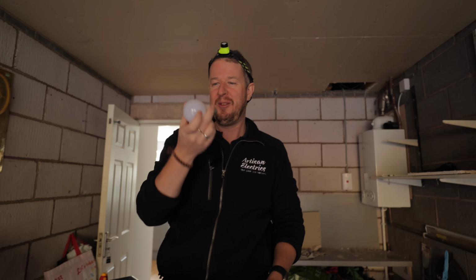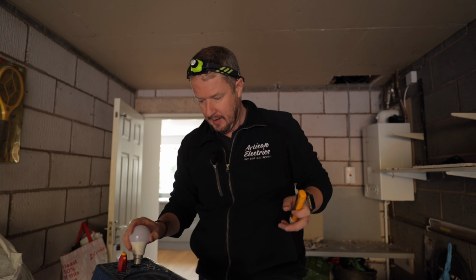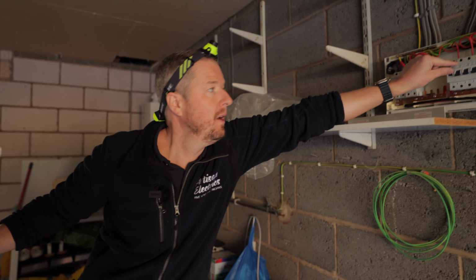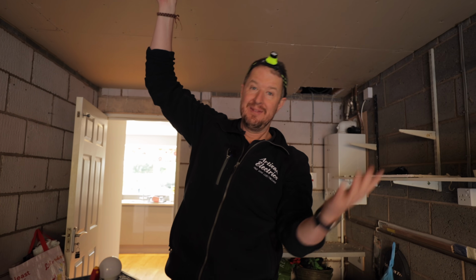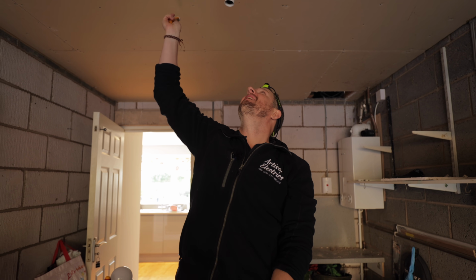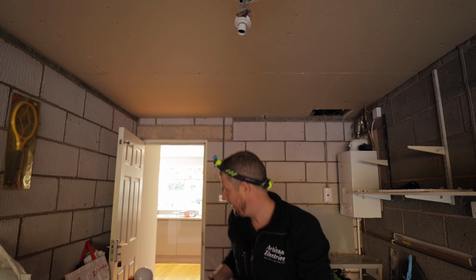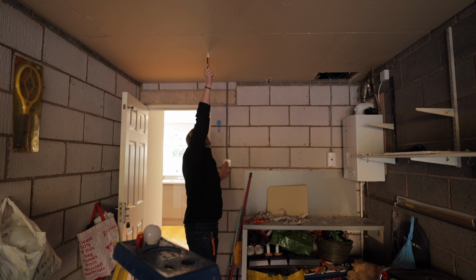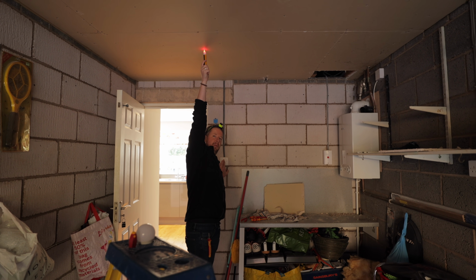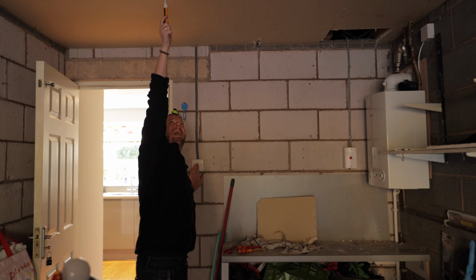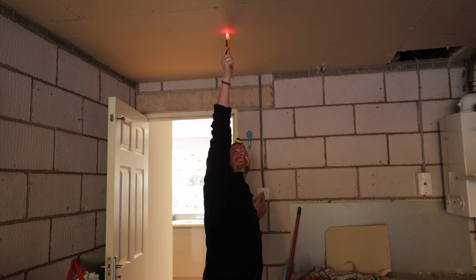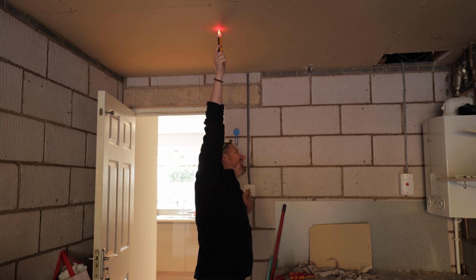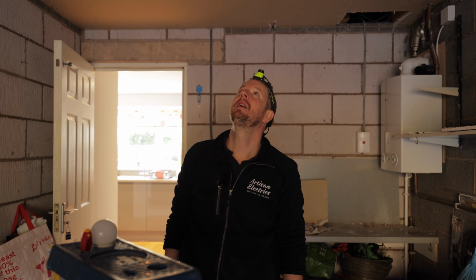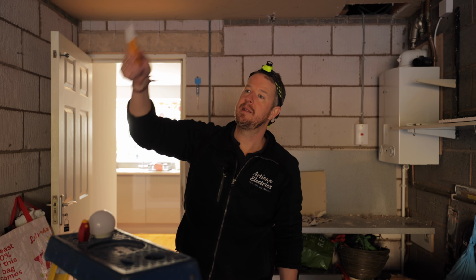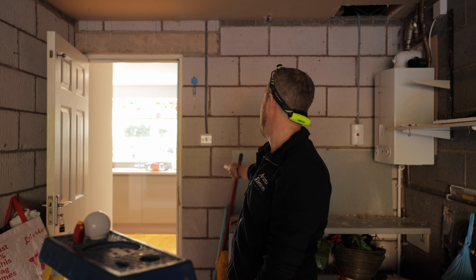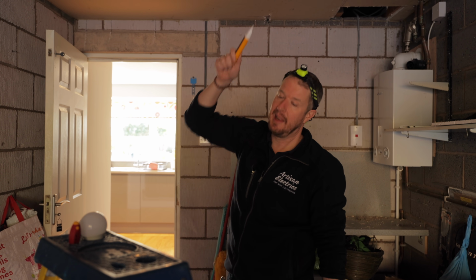So I've removed this LED lamp. I'm going to turn the circuit back on now. We still have a problem. So it's actually the fact that the light circuit is switched on is the problem. Look at that. That is so crazy. Have you ever seen anything like this? There's obviously some kind of issue with the switch wires. So it's either that cable from there to there, or the cable from here to the light.